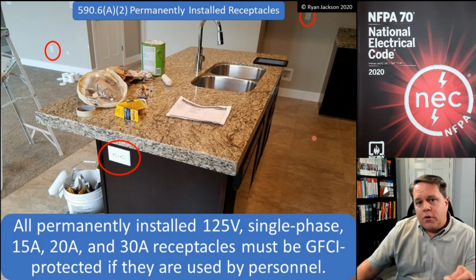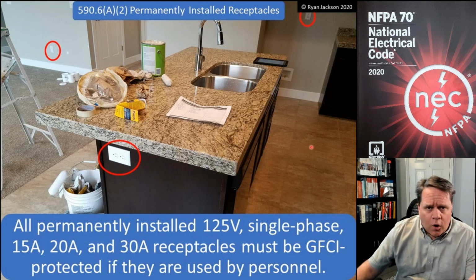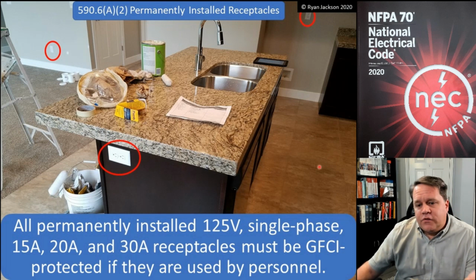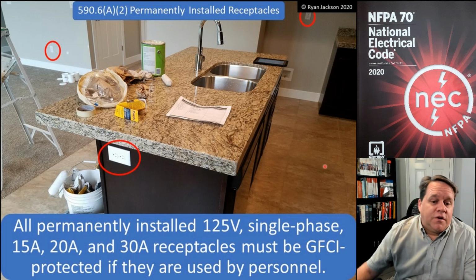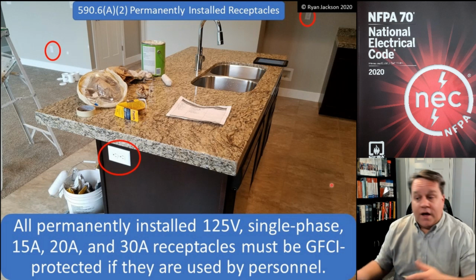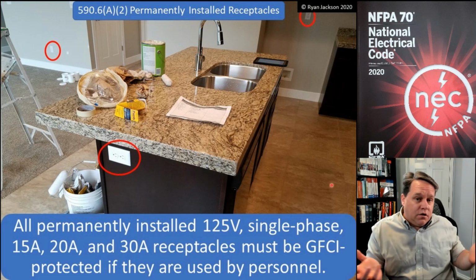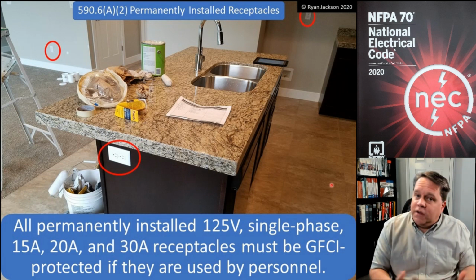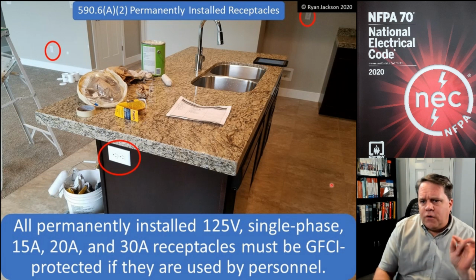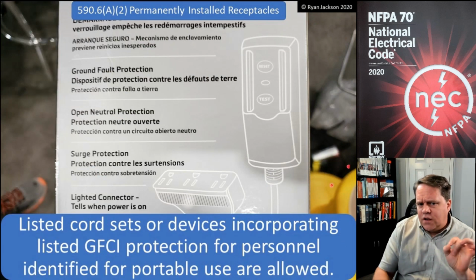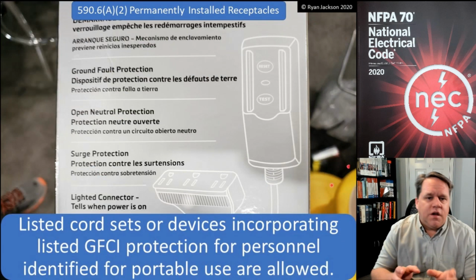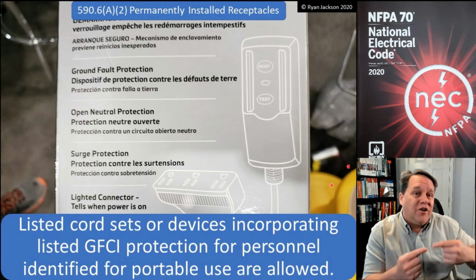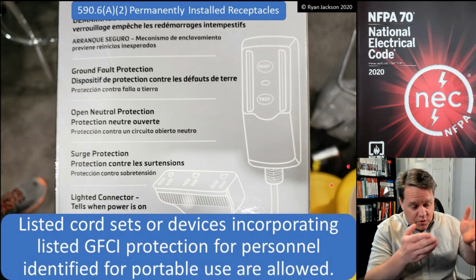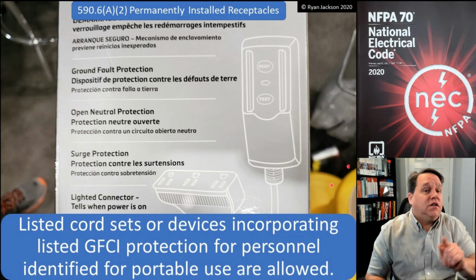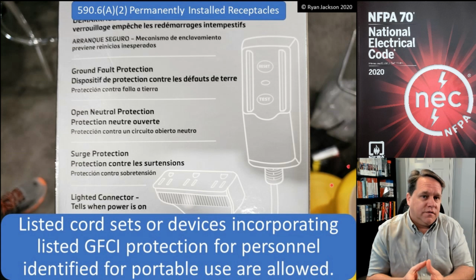So what are the rules for permanently installed receptacles? Well, all permanently installed 125 volt single phase, 15, 20, or 30 amp receptacles must be GFCI protected if they're being used by personnel. Okay, so it doesn't matter if they're part of the building or not part of the building, we have to have GFCI protection. But if you read in this section, it's written a little bit differently. You see, in A1, the receptacles that are not permanent, it says, hey, you have to have GFCI protection. And in addition to that, you can use portable devices.